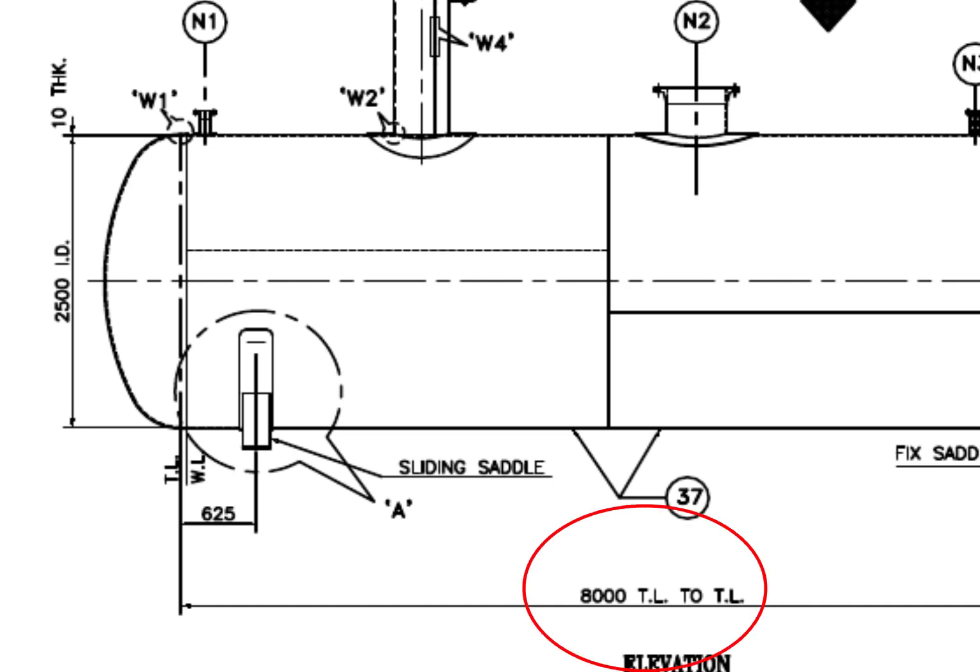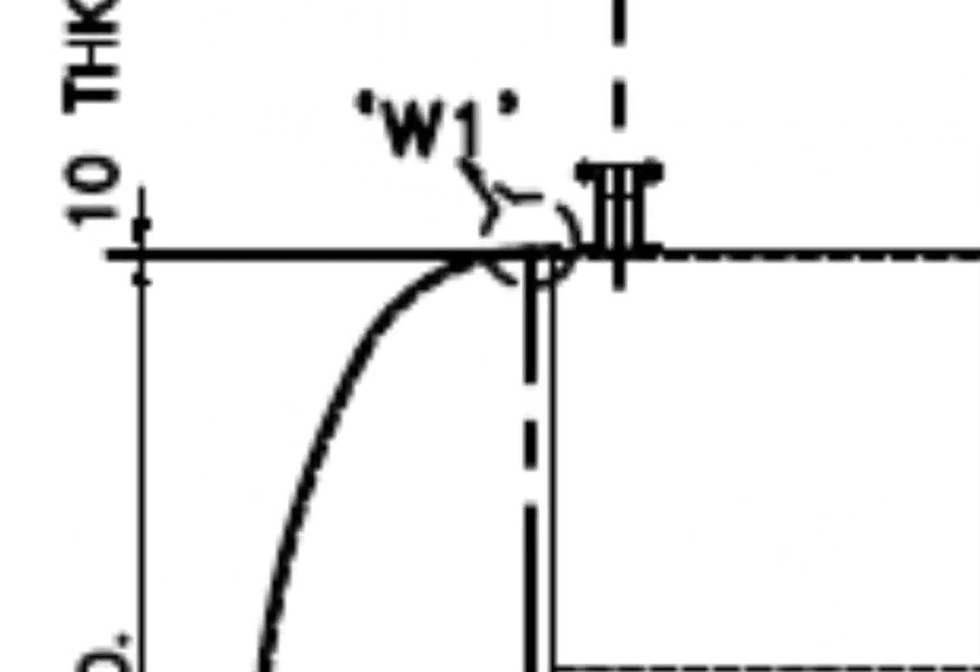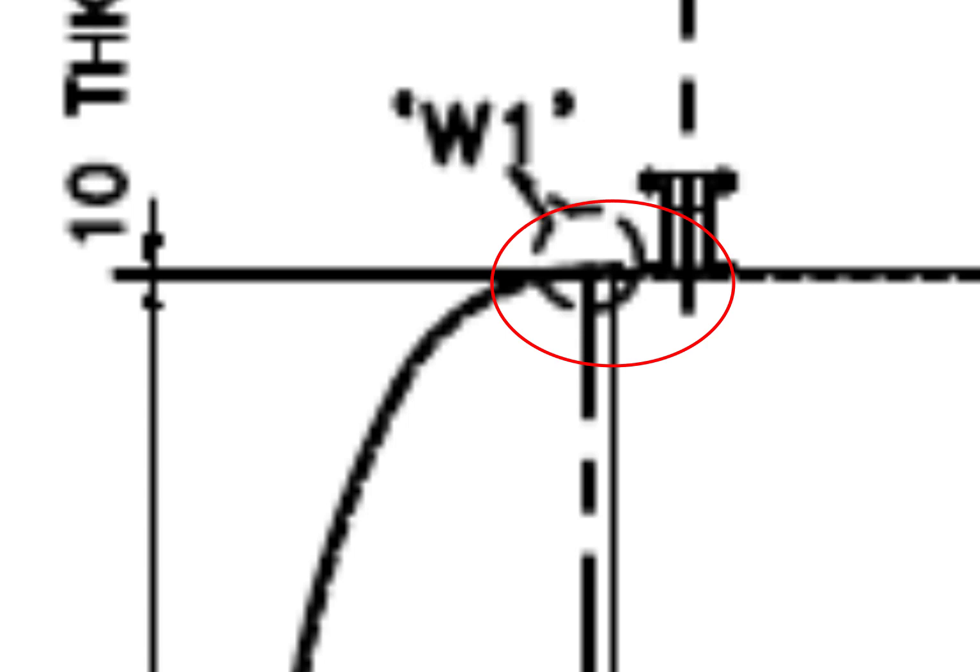TL to TL length is 8,000 mm. What is TL? TL is tangent line or tangential line. What is a tangent line? The tangent line describes the point on the head where the knuckle radius meets the straight flange.